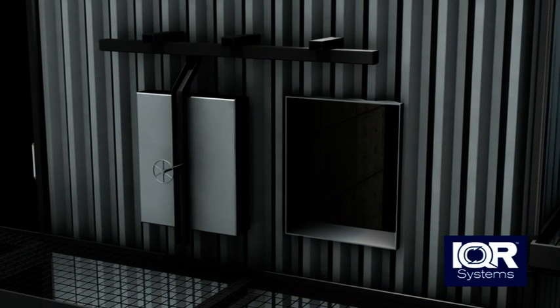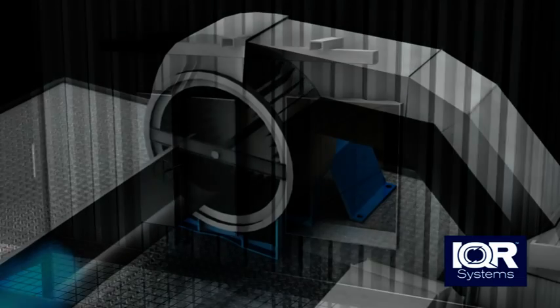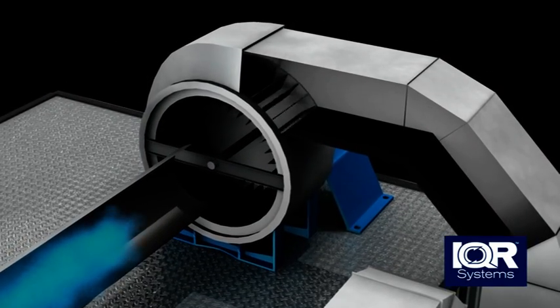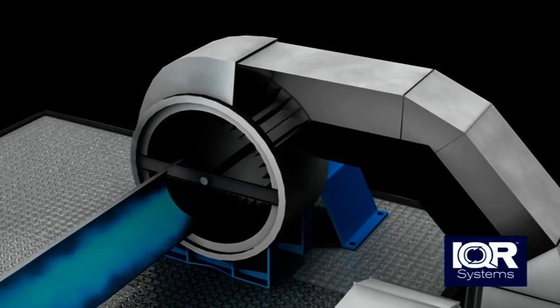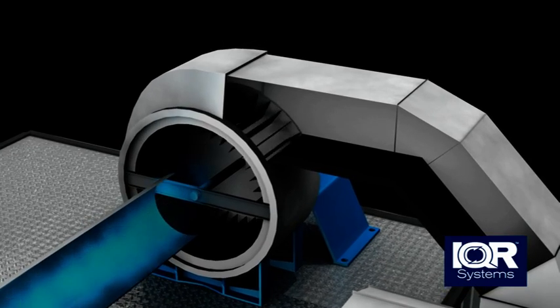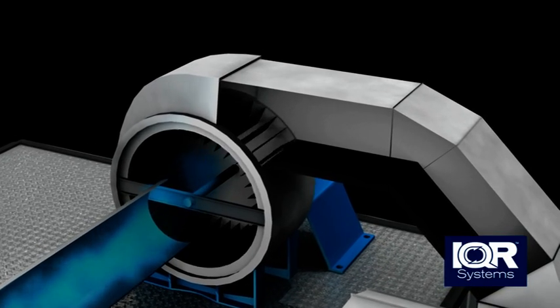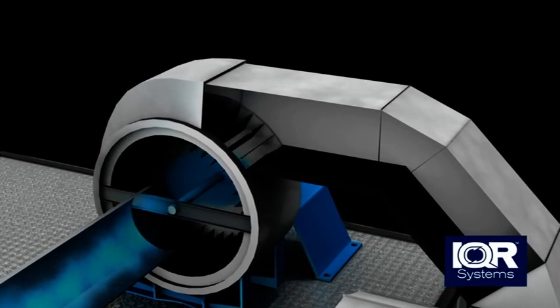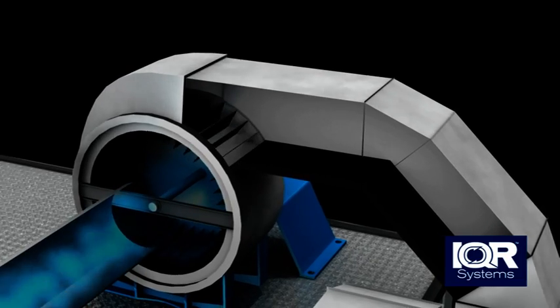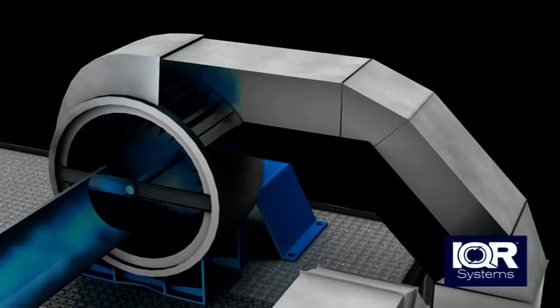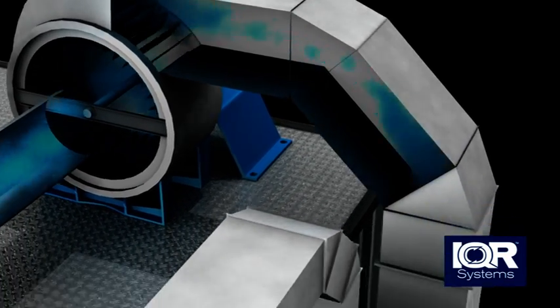The doors are in the open position when the unit starts. SFC, soot free combustion unit, is a co-current gasifier. The technique implies that the combustion air is added where the coldest fuel is situated, and the produced gas leaves the fuel bed from its hottest point.